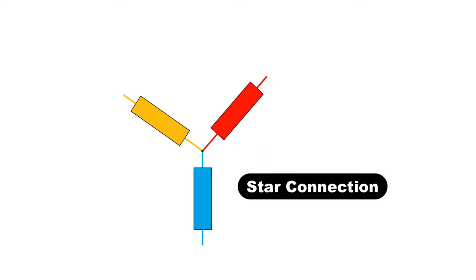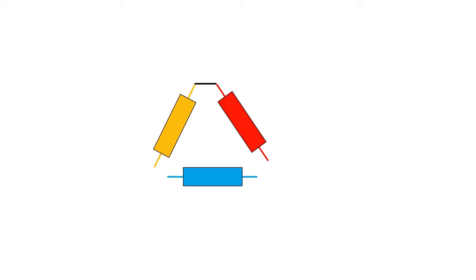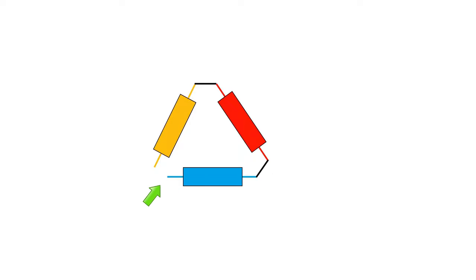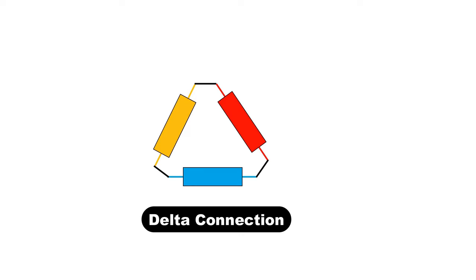Now if you want to connect motor winding in delta, then what you have to do is connect the motor windings in series. Take one end of a winding and connect with one end of another winding. Similarly, take the other end of the same winding and connect with one end of the third winding. If you connect motor winding in this way, then it will be known as delta connection. And if you connect it the other way, it will be known as star connection.